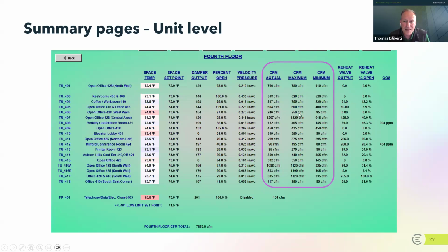But this is the number one thing that I see changed by people in the field when there are occupants that are uncomfortable. They will change these airflow settings because they want to make a little more airflow in there. They want to make it a little bit hotter. They want to make it a little bit colder. They want to reduce these things. And in the process, it gets the system all out of whack. So the main takeaway on this is if you have sophisticated VAV systems with terminal units or VAVs, you have to go back to the answer key, to the MEP documents, and find out how it was designed and how it's supposed to be operated, because very likely your system is not running the way it was supposed to be operated.